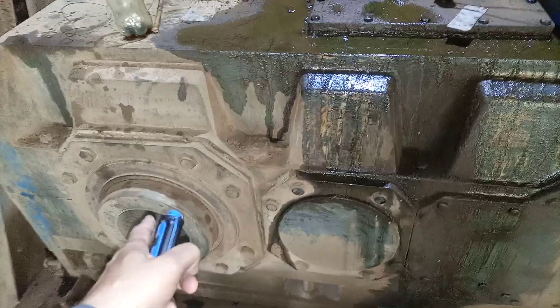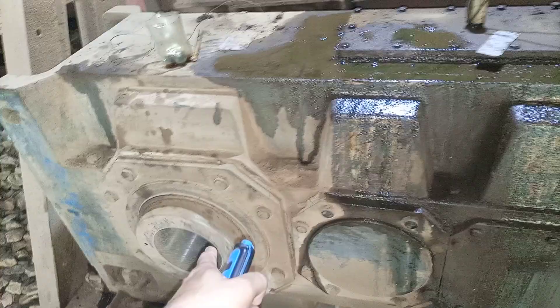The vertical is also okay at 2 millimeters per second. This is the reduction stage — a three-stage gearbox with input, first stage, second stage, and third stage. It runs at very low speed on the output side and high speed on the input side.